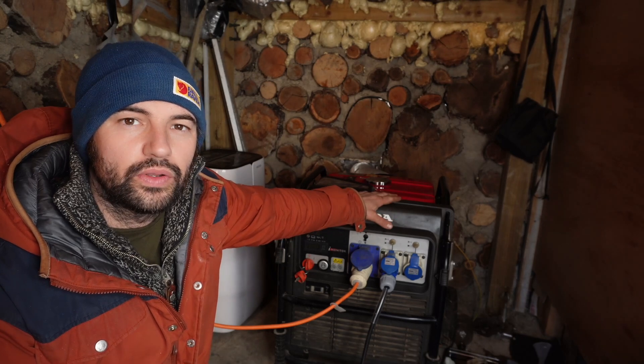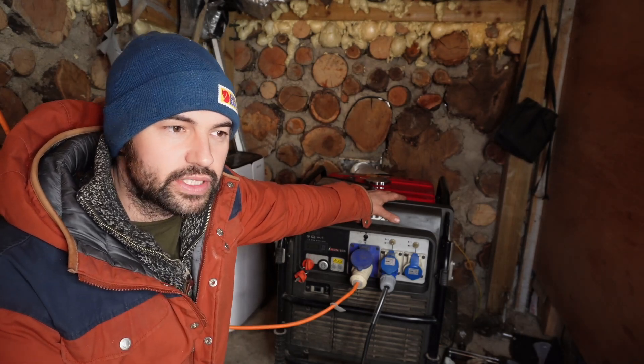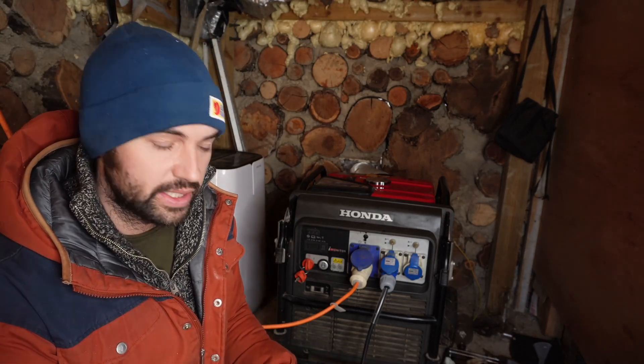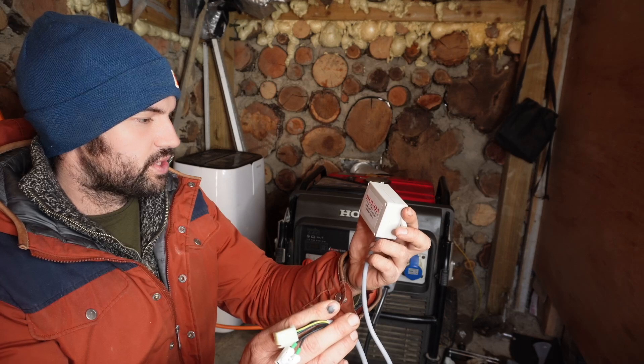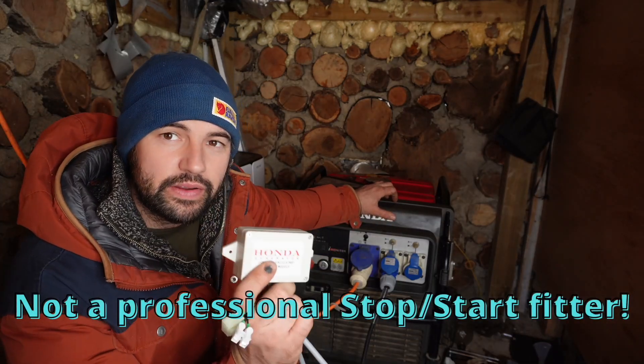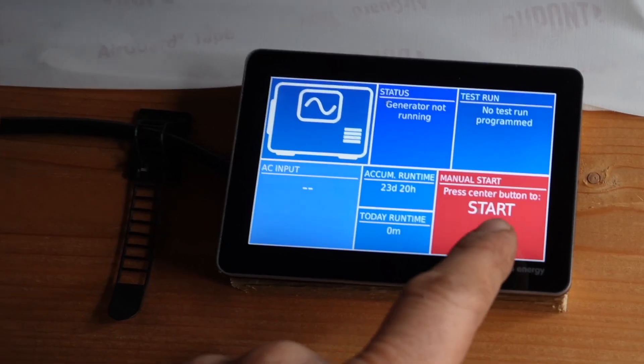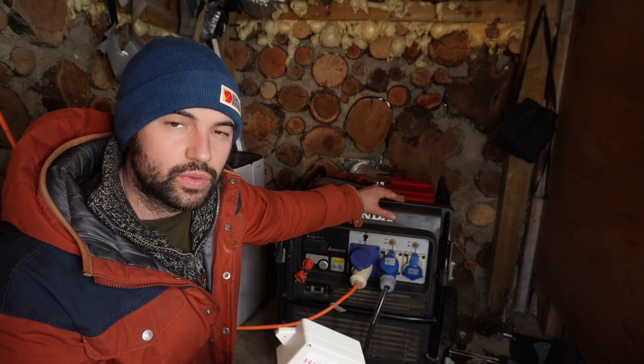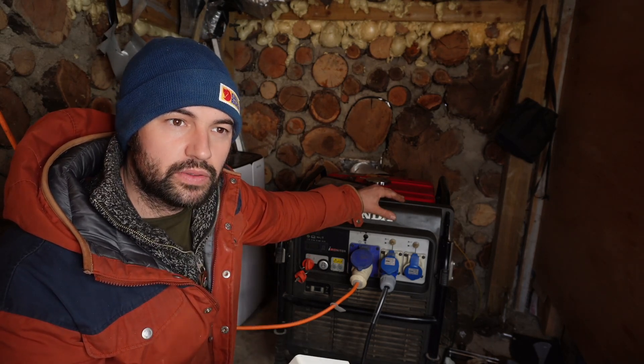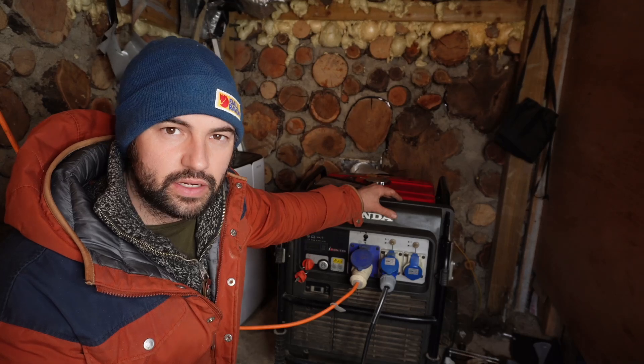That incident gave me more urgency to set up a system where the generator comes on automatically when the batteries drop below 20%, tops them up, and then switches off. It's not ideal when anything like that happens, but it's even worse if you come back and your batteries have been completely depleted. I've bought an auto-start kit — I'm hoping it will work with the Cerbo GX so you can start and stop the generator and have it come on automatically at 20%, charging up to around 40-50% before switching itself off.